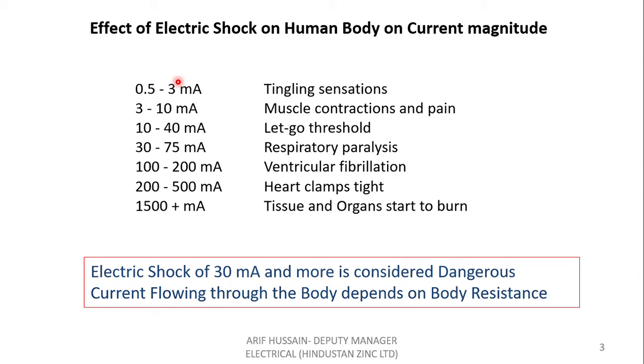Now let us see the effect of electric shock on the human body at different magnitudes of current. At 0.5 to 3 milliamperes, it will give just a tingling sensation and nothing else — perfectly fine. At 3 to 10 milliamperes, our muscles will start contracting and we will feel pain. At 10 to 40 milliamperes, it is called the let-go threshold, which means the victim who got a shock of around 40 milliamperes won't be able to rescue himself.